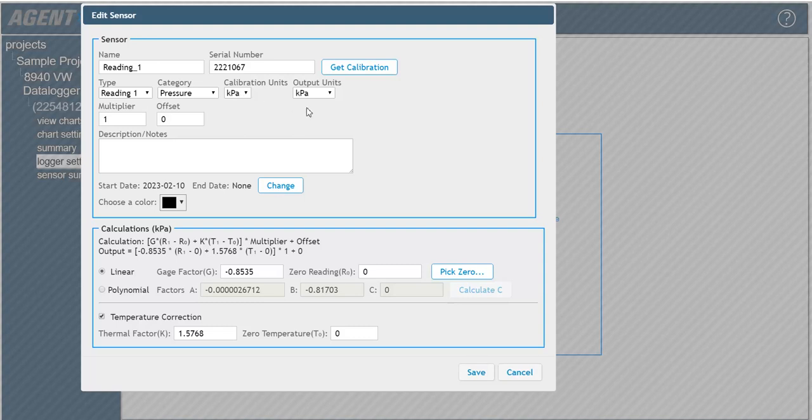Enter the initial zero reading that was taken on site with the vibrating wire sensor. If using the 8940 to collect the initial zero reading, save the information entered into the form, then download the data from the data logger. Return to the sensor edit screen and click pick zero, then select one of the readings taken from the data logger to use as the initial on site zero reading.